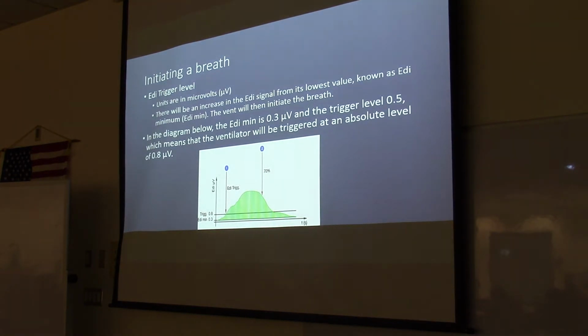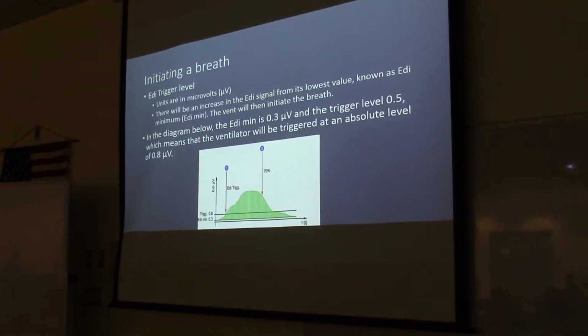So to initiate a breath, it says there's first an EDI trigger level in microvolts. There will be an increase in the EDI signal from its lowest value, known as EDI minimum or min, and then the ventilator will initiate the breath. All right, I need to explain that to you.